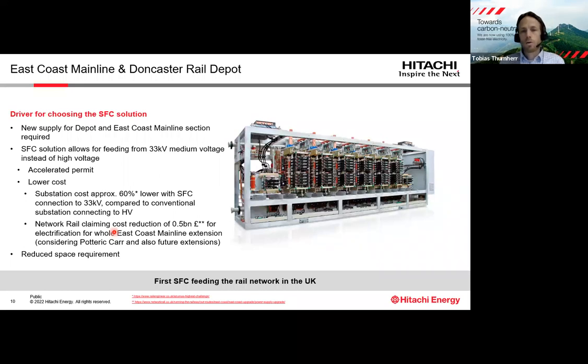It also means a lower cost. So for SFC, for Potteric Carr, we are talking about a 60% lower substation cost because of the connection to 33 kV compared to a high voltage connection. And actually Network Rail also claim a cost reduction of the whole East Coast Mainline extension. So that's not only the Potteric Carr project, but also future extensions, a total cost reduction there of around £500 million. So it's quite a big saving that can be achieved with the rail SFCs in this example. And then last is that because of the connection to medium voltage instead of high voltage, we can also have a reduced footprint.